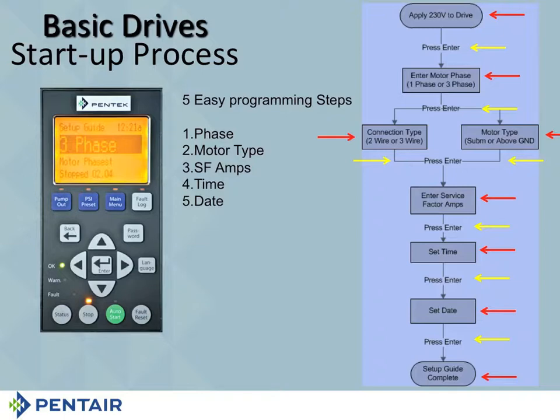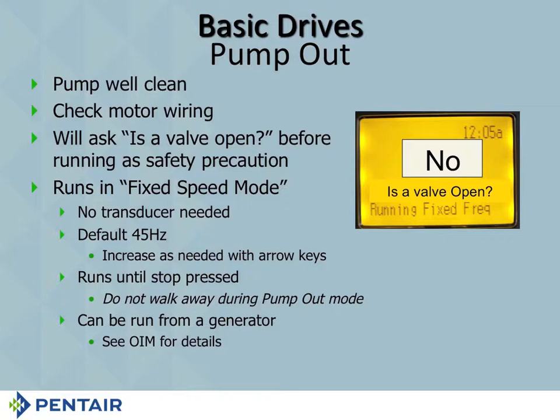None. So pump out. Remember what I said, pump out is one of those blue buttons, all right? It has a very, very important function. So it starts out with the question, is a valve open? The answer is no. You have to do one of 2 things, or maybe you have to do 2 of 2 things. You have to open a valve and then change the no to a yes. If you don't open the valve and you say yes, you're accepting responsibility for burning the motor up, because now you're going to deadhead the pump. If you open the valve and then say yes, it will turn on.